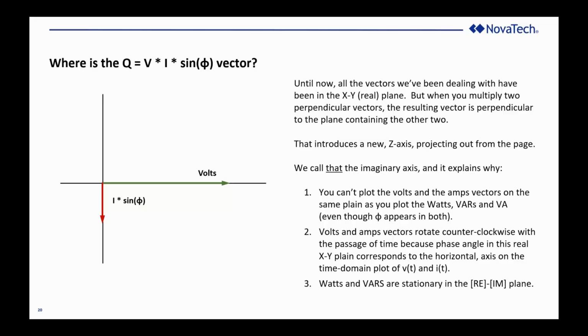So you can't plot the volts and the amps vectors on the same plane that you plot the watts and the VARs. You may have noticed a lot of times we see an XY plane used to represent volts and amps, and we see an XY plane used to represent watts, VARs, and VA. But they're not the same plane. You can't plot the voltage and the current on the watts and VARs plane, because the watts and VARs plane is the XZ plane and not the XY plane. So as long as you're in the XY plane, the vectors that you're looking at rotate counterclockwise, and you'll see the sequence of voltage and current, but you don't see the VARs. You could see the watts, that would be rotating, but you have to move into the XZ plane to see the VARs.